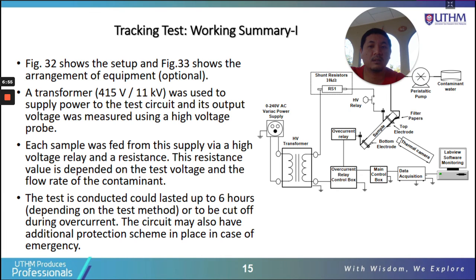So it is basically supposed to match the resistance of the sample. The test is conducted and could last up to 6 hours, depending on the test method. Basically, we have to look at the standards. What is the standard's requirement? If it can withstand up to 6 hours, there's no problem. There's no flashover, there's no hole, and the leakage current is less than 60 milliamp, then it passed the test. So we have to check on the test method and on the standard, ASTM and so on.